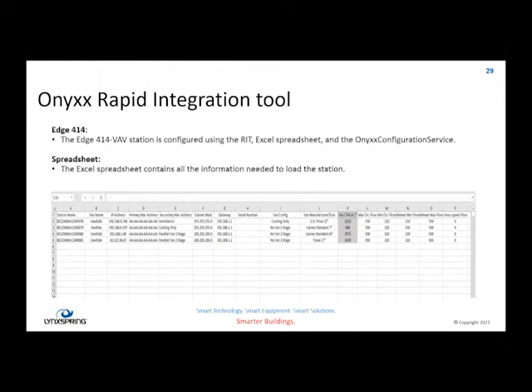We tell what type of VAV it is, which one of the 27 configurations we use, what type of box it is, how large it is, your CFMs at 1 inch, that's how you calibrate your box, min-max flows, type of thermostat. All that information is collected into the spreadsheet. That spreadsheet is then used by the integration tool to build your stations.